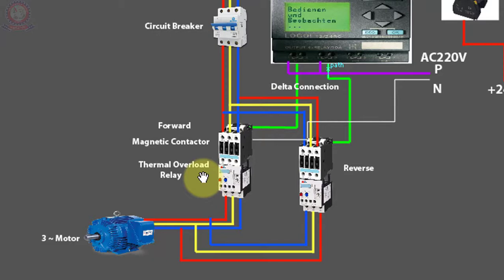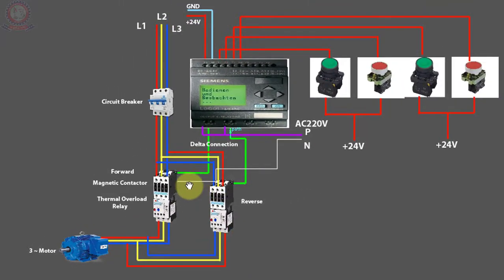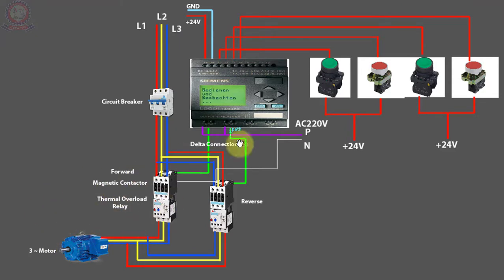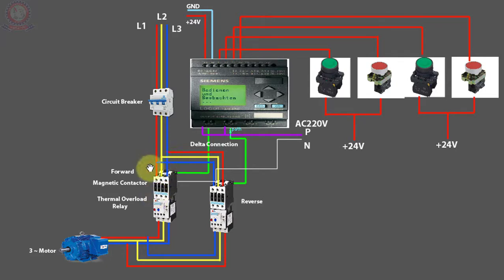We have a simple ladder diagram. If we energize the forward magnetic contactor, the motor starts forward. If we press the stop button, then press the reverse button, we press I3 to activate the reverse magnetic contactor. This contactor changes the wiring combination, which changes the rotation direction, and the motor will reverse.